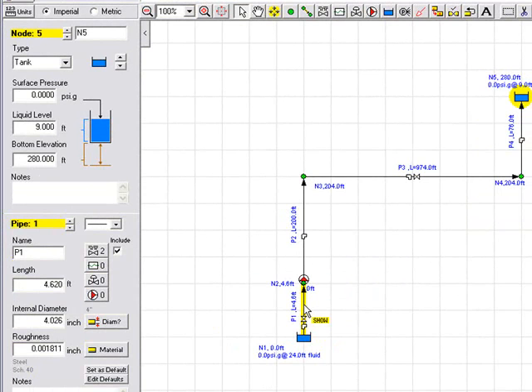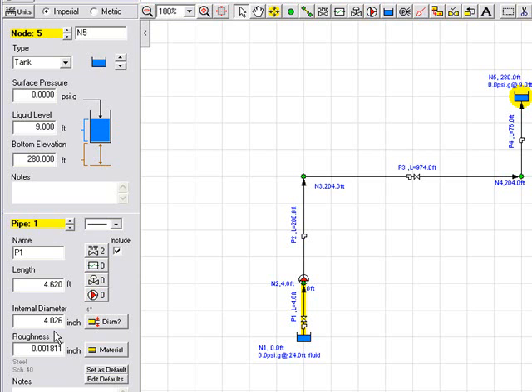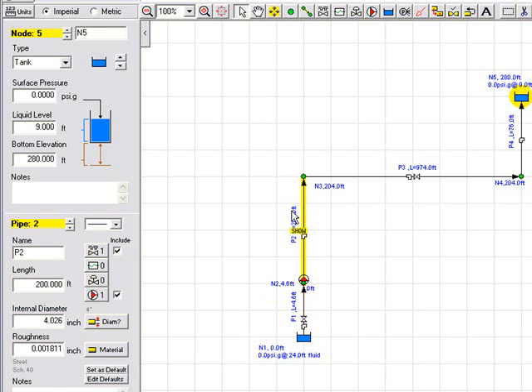If we highlight pipe 1, we can see the details of the pipe. This has a length of 4.62 feet. It's a 4 inch pipe with an internal diameter of 4.026 inches. And we have selected schedule 40 steel and this is the roughness value. We can highlight other pipes in the system and review the length of the pipes and the diameters and the roughness. All the pipes are set to be 4 inches and again all use schedule 40 steel.